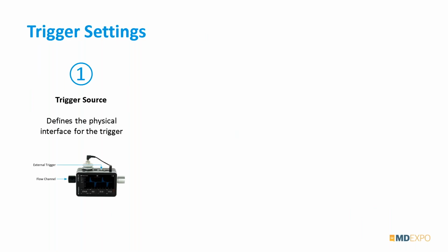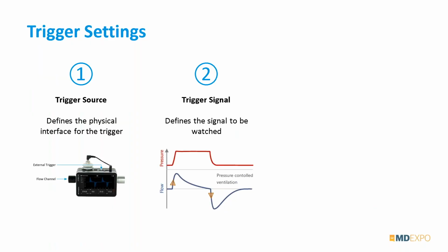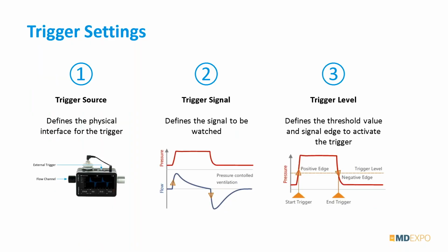So how can we define trigger settings? Typically in a gas flow analyzer, you will see three different settings: the trigger source, the trigger signal, and the trigger level. As a trigger source, we can typically select between a flow channel of the device or a pressure port. Sometimes you will also see an external trigger input.